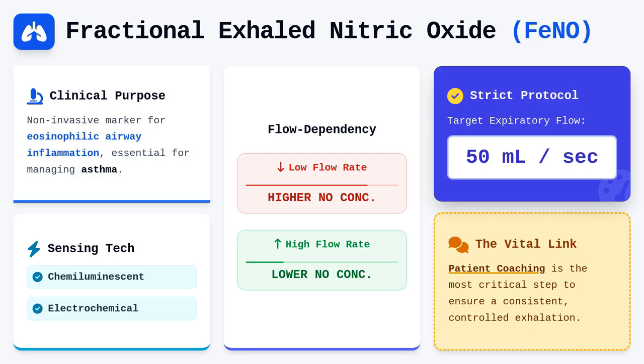To obtain a valid measurement, the patient must maintain a steady expiratory flow rate, generally held at 50 milliliters per second for a specified time interval. This flow rate is significant because the concentration of nitric oxide in the exhaled air is flow dependent. It is higher at lower flow rates and lower at higher flow rates. Therefore, coaching the patient to maintain a consistent, controlled exhalation is perhaps the most difficult and vital aspect of the test.